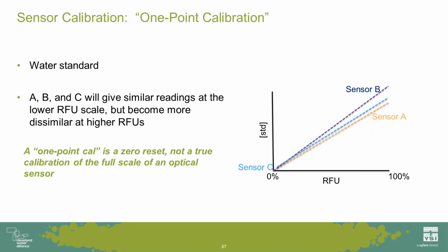So I want to address some language, and Saul, this might at least partially address your question that you gave us in the last section, that we use in the industry regarding calibration. Very often you will hear people refer to a one-point calibration. Now, I grew up in the lab world. I'm a lab rat by training, and in my mind, 1 point is not actually a calibration, though in some cases it's appropriate to do that.